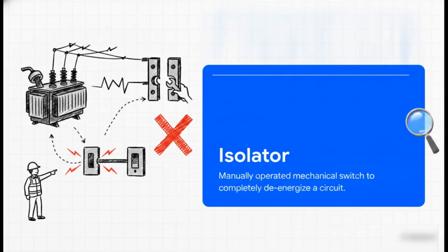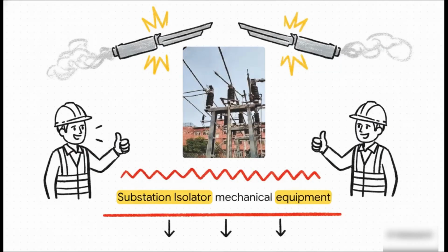Obviously, a crew can't just walk up to a live high-voltage wire. That's where isolators come in. An isolator is a manually operated mechanical switch used to completely physically disconnect a section of the circuit. But here's the really important catch. Isolators do not have any arc quenching capability. That means you can only open that when the current has already been safely switched off by another device somewhere else. Despite being a relatively simple, cheaper manual device compared to the more complex automated components, the isolator is absolutely vital for human safety. When maintenance crews see those giant metal arms physically swing open, they have 100% visual proof that the power is cut off from the equipment they're about to work on.